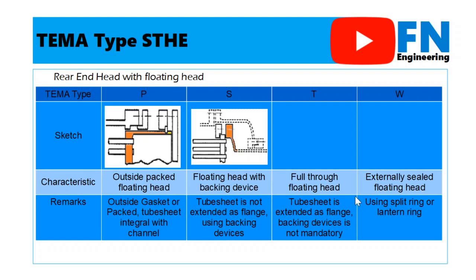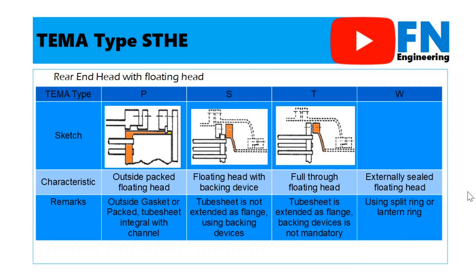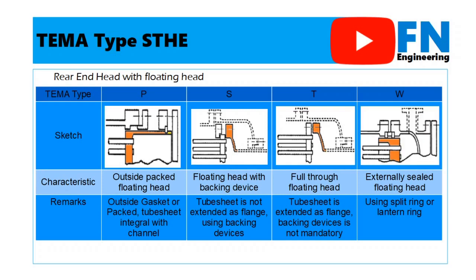Next, type S is a floating head with backing device. It means the tubesheet is not extended as a flange because we use a backing device to prevent leakage between the shell side and tube side. The next type is type T. Type T uses a tubesheet extended as a flange, so the backing device is not mandatory or is not required. The last is type W. It is similar to type P, but this type uses a split ring or lantern ring between shell flange, channel flange, and tubesheet.